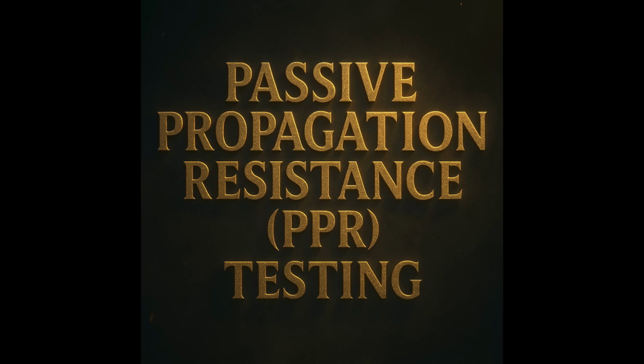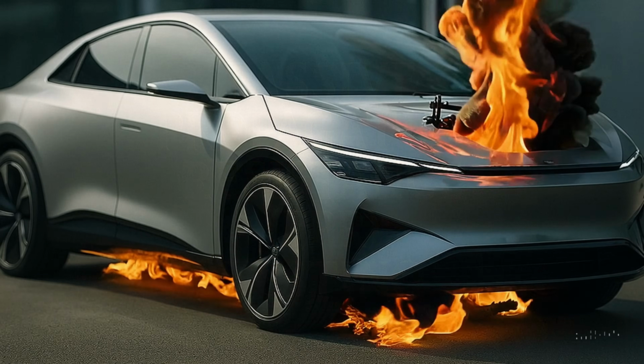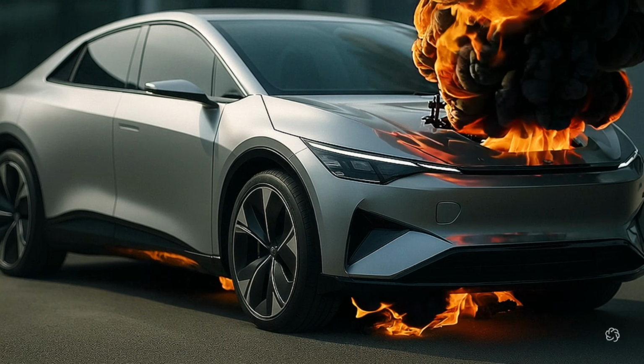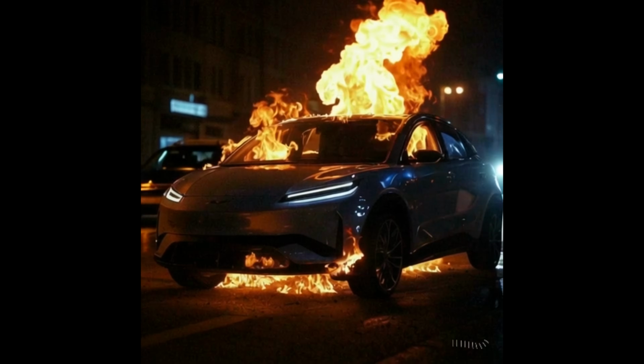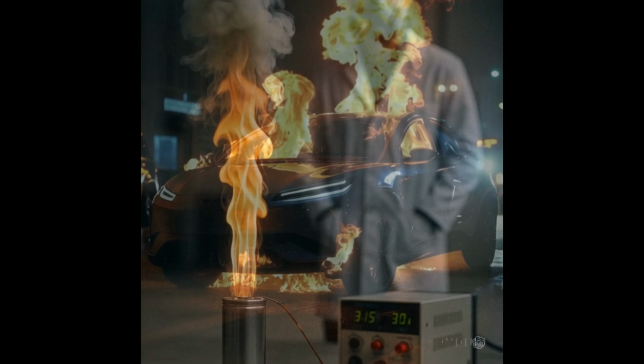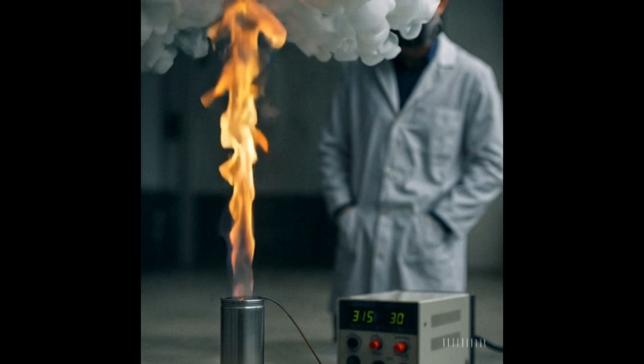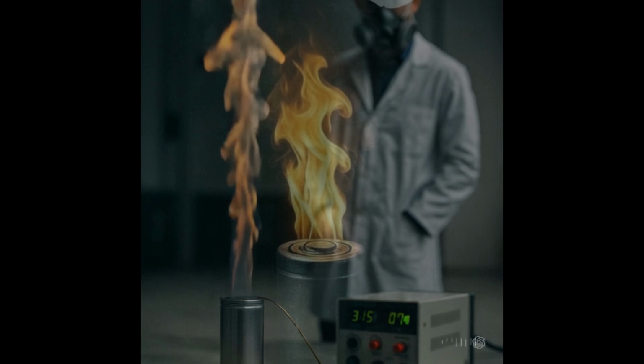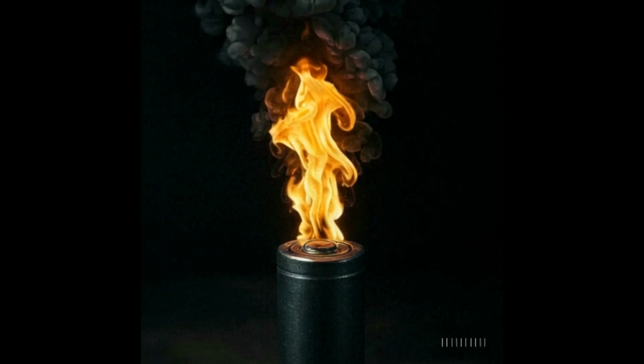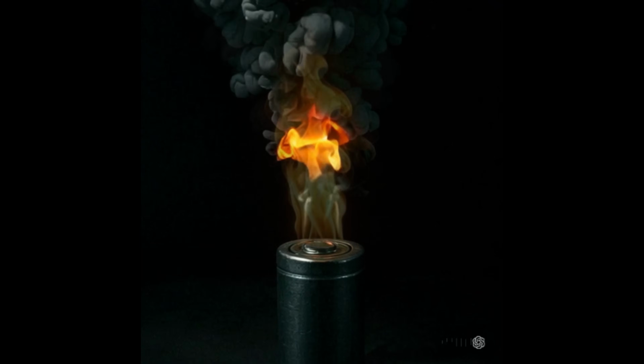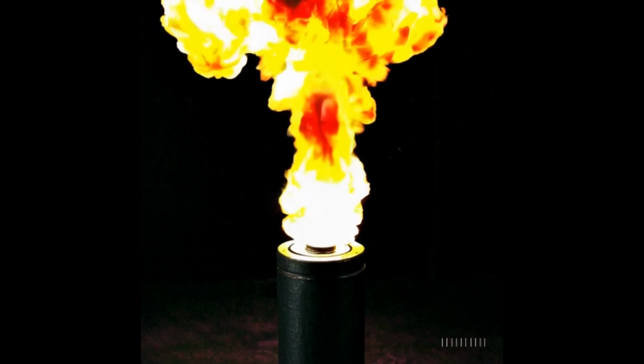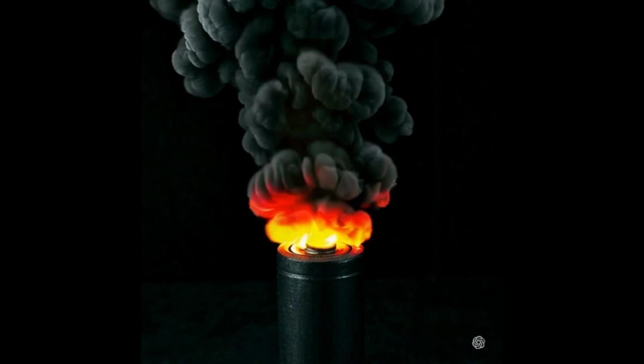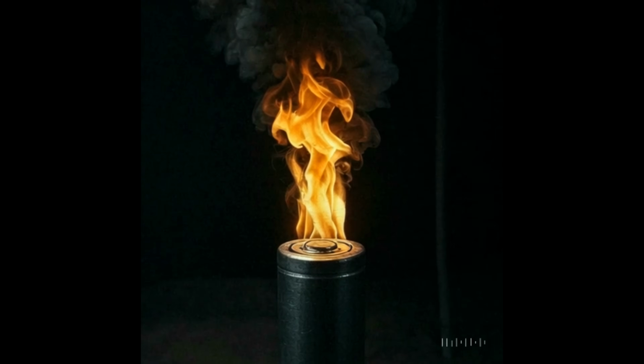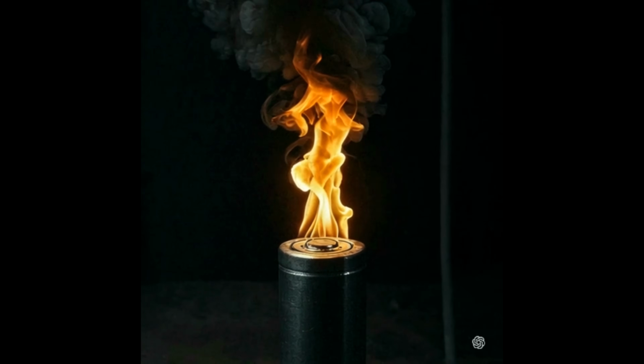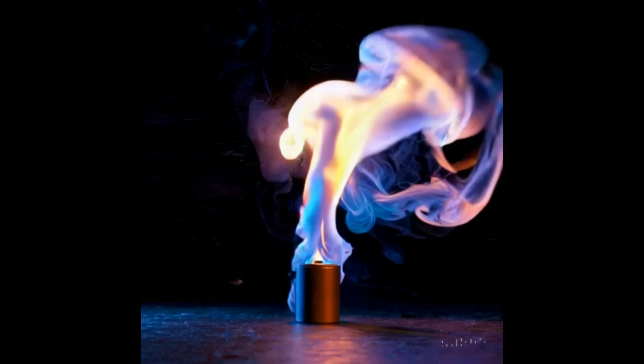Let's look at passive propagation resistance, or PPR testing. Here's a test that separates well-engineered packs from the rest. If a single cell goes into thermal runaway, can the rest of the pack survive and contain the thermal event? With the amount of energy contained in such a small package, thermal runaway can happen. The key is to limit or even prevent thermal runaway propagation, which means the spread of heat and fire to neighboring cells within a battery pack when a single cell goes into thermal runaway.